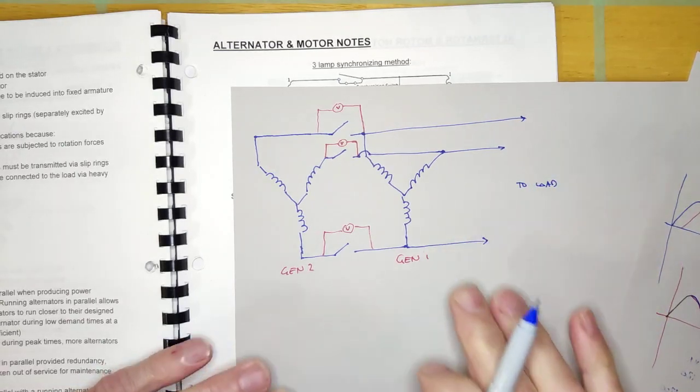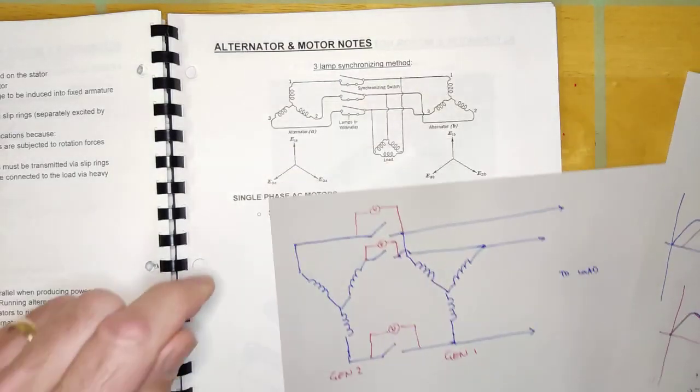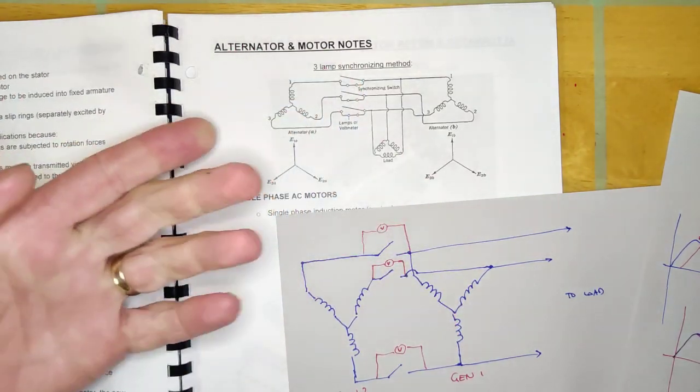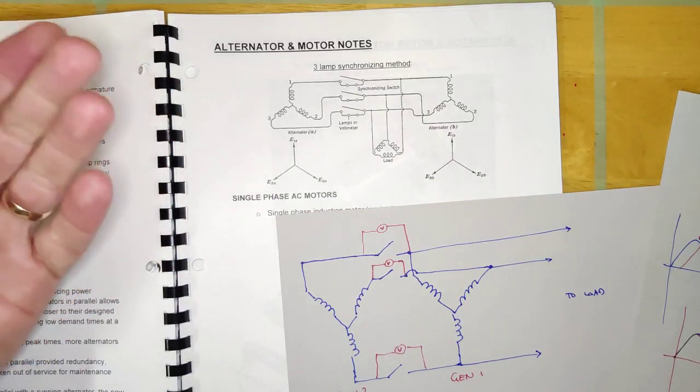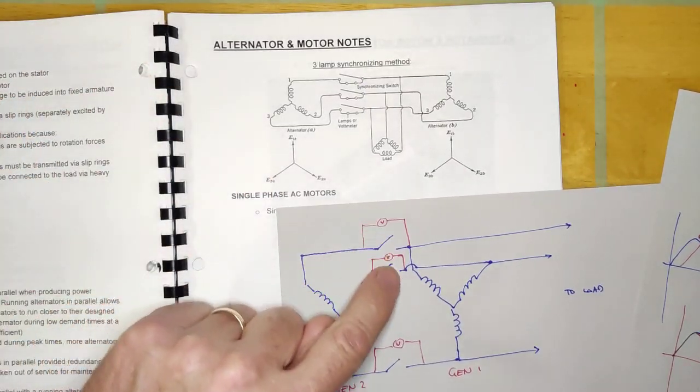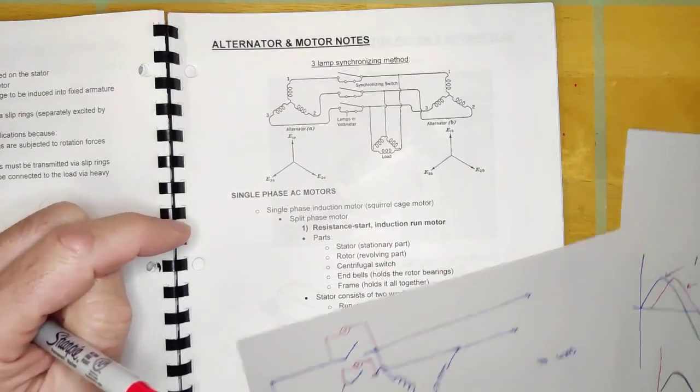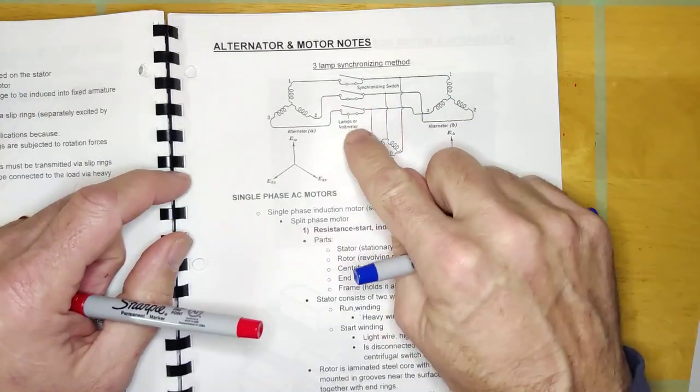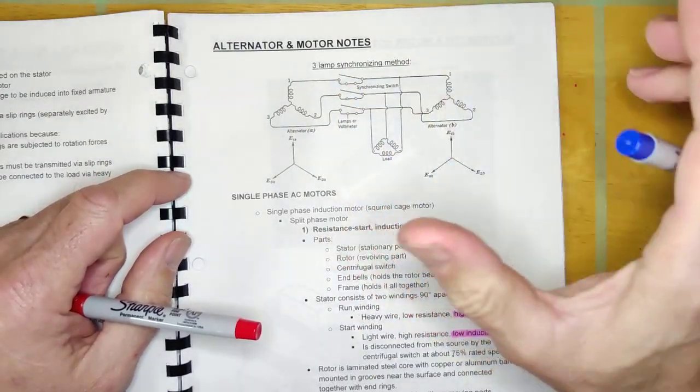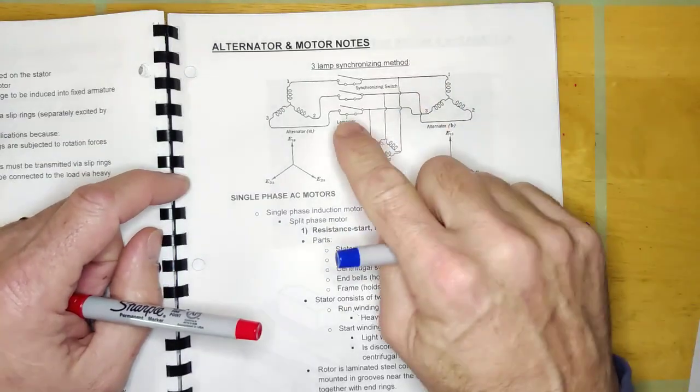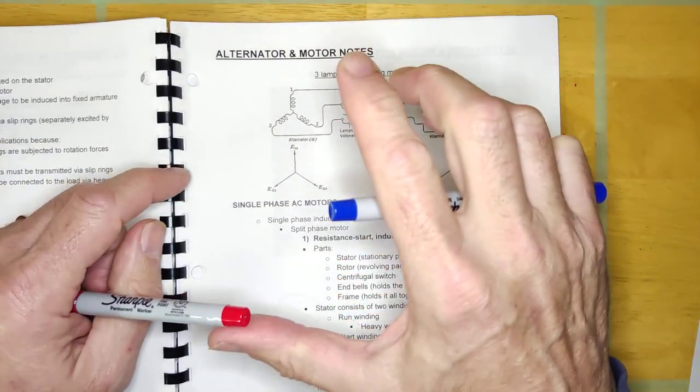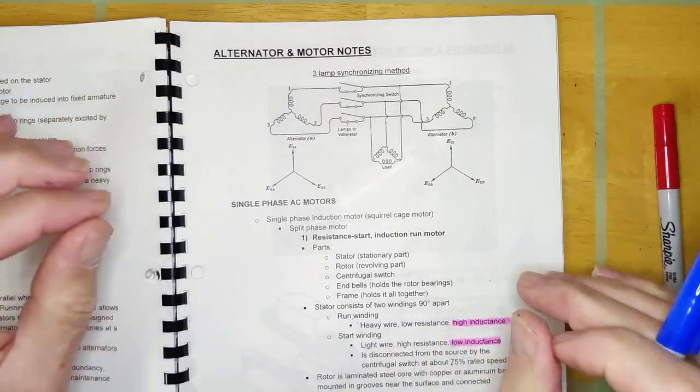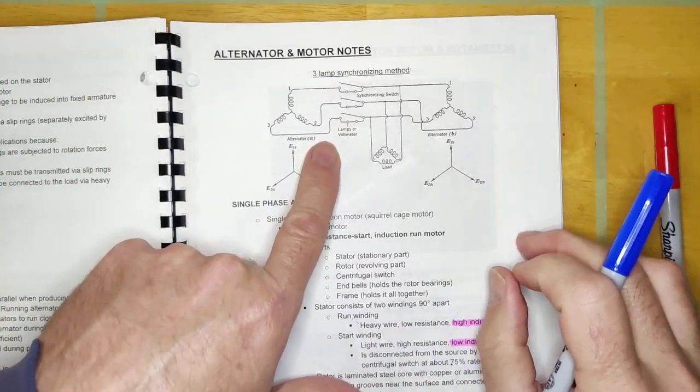That's what the three lamp method is - here they show voltmeters or lamps, and when the lamps go out you know everything is cool and you can close the switch. To me, voltmeters seem more practical. Now I'm fully aware you will never see anybody doing this manually because this is going to be fully automated at Bruce Nuclear or wherever. There's going to be equipment synchronizing everything and then automatically closing the switch.